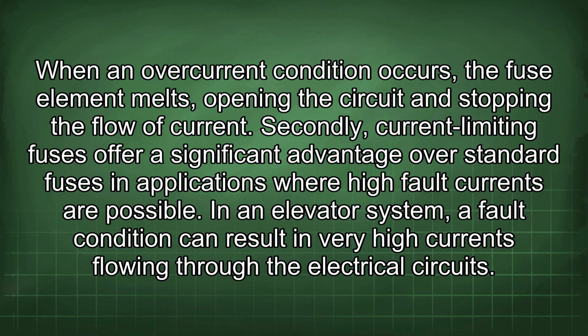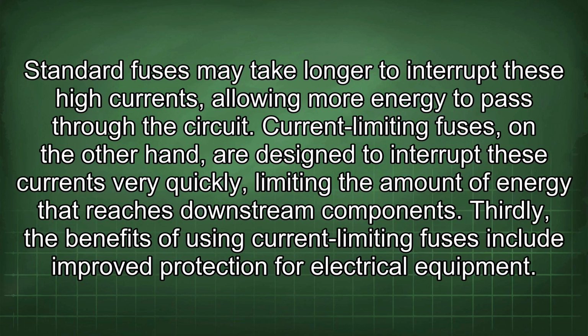In an elevator system, a fault condition can result in very high currents flowing through the electrical circuits. Standard fuses may take longer to interrupt these high currents, allowing more energy to pass through the circuit. Current-limiting fuses, on the other hand, are designed to interrupt these currents very quickly, limiting the amount of energy that reaches downstream components. Thirdly, the benefits of using current-limiting fuses include improved protection for electrical equipment.